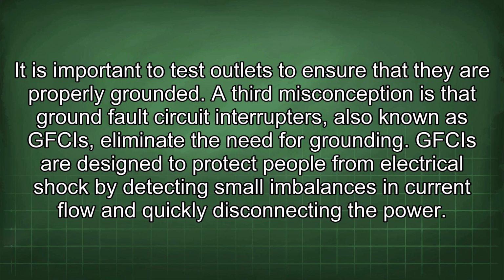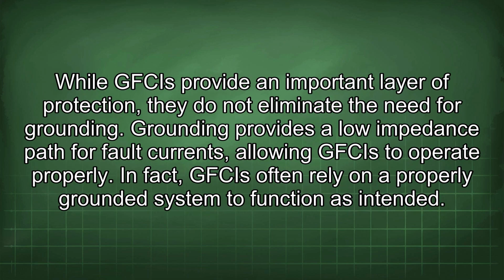A third misconception is that ground fault circuit interrupters, also known as GFCIs, eliminate the need for grounding. GFCIs are designed to protect people from electrical shock by detecting small imbalances in current flow and quickly disconnecting the power. While GFCIs provide an important layer of protection, they do not eliminate the need for grounding. Grounding provides a low-impedance path for fault currents, allowing GFCIs to operate properly. In fact, GFCIs often rely on a properly grounded system to function as intended.